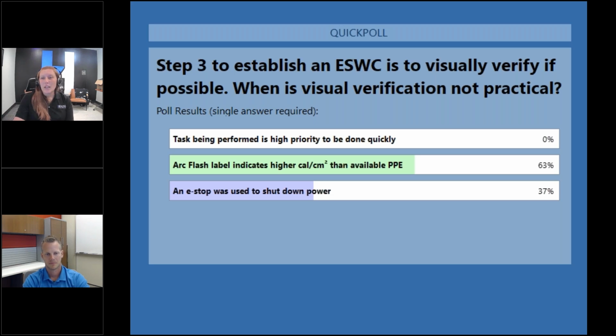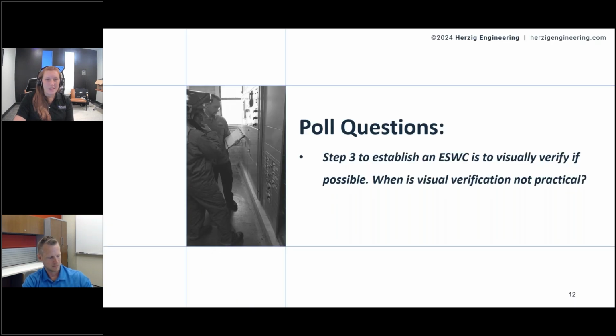The last one though, an e-stop used to shut down the power. Oftentimes, I don't think e-stops really shut down the power. They stop the moving components. I've seen that plenty of times. If your e-stop does actually shut down power, great for emergency situations, not for verifying an electrically safe work condition. You actually have to physically isolate that disconnect point, and an e-stop is not designed to do that. Okay, so we'll go ahead and go to the next step. So visually verify if possible.